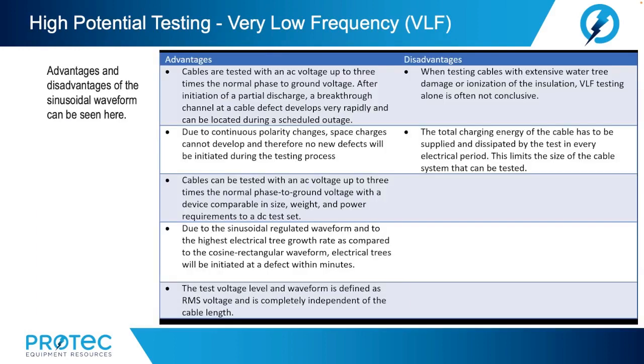Now let's review the advantages and disadvantages of the sinusoidal VLF waveform. Among the advantages, cables are tested with an AC voltage up to 3 times the normal phase to ground voltage. After initiation of a partial discharge, a breakthrough channel at a cable defect develops very rapidly and can be located during a scheduled outage. Another advantage, due to continuous polarity changes, space charges cannot develop and therefore no new defects will be initiated during the testing process. Also among the advantages, cables can be tested with an AC voltage up to 3 times the normal phase to ground voltage, utilizing a device comparable in size, weight, and power requirements to that of a standard DC test set.